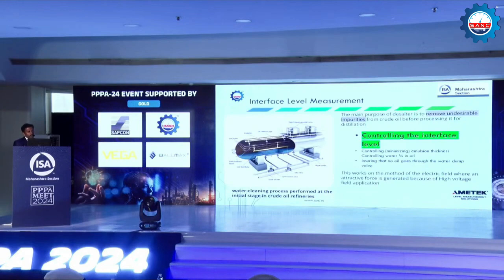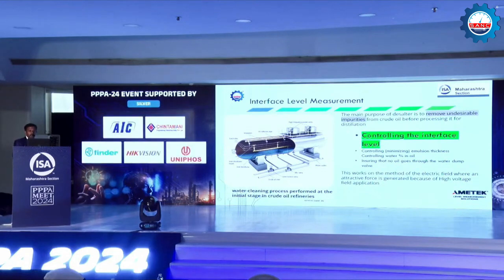There are a few applications where this RF admittance technology works really well, one of which is interface level measurement in a desalter. In desalters, it is always mandatory to keep the interface level at a particular level. The primary aim is to control the interface level so that the oil does not go through the water dump valve.